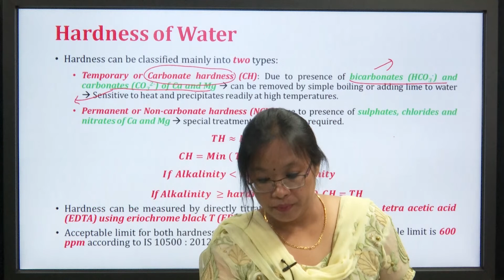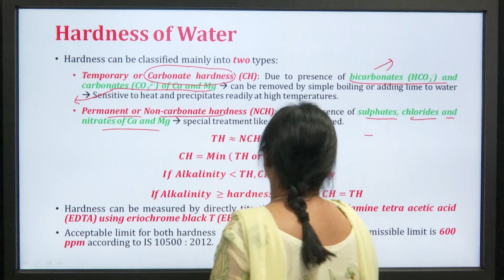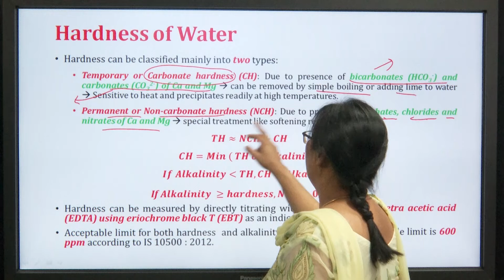Another is permanent or non-carbonate hardness, which is due to the presence of sulphates, chlorides and nitrates of calcium and magnesium. Bicarbonates and carbonates of calcium and magnesium cause carbonate hardness, and sulphates, chlorides and nitrates cause non-carbonate hardness. Why is carbonate hardness called temporary? Because it is very easy to remove. It can be removed by simply boiling or adding lime, while non-carbonate hardness requires special treatment like softening.